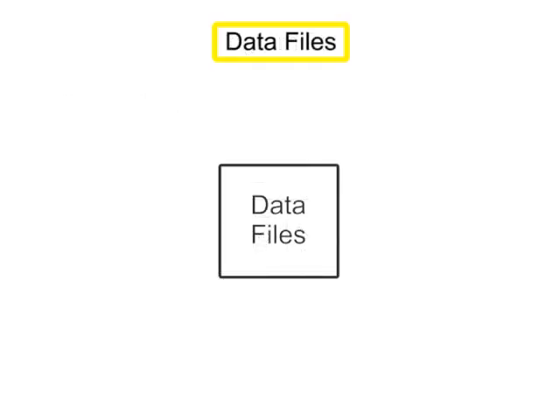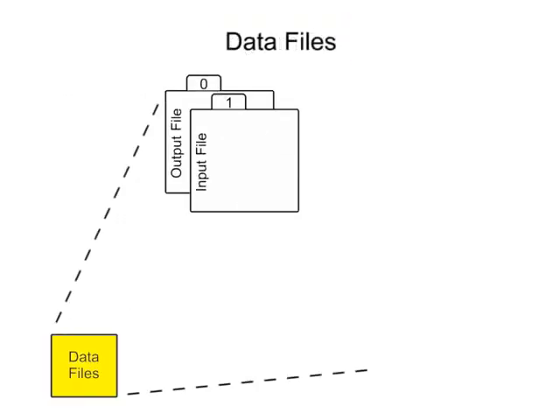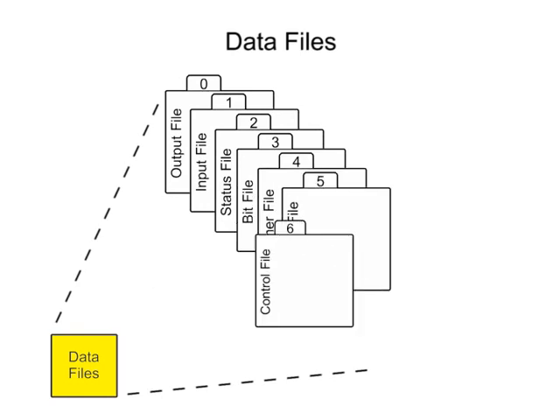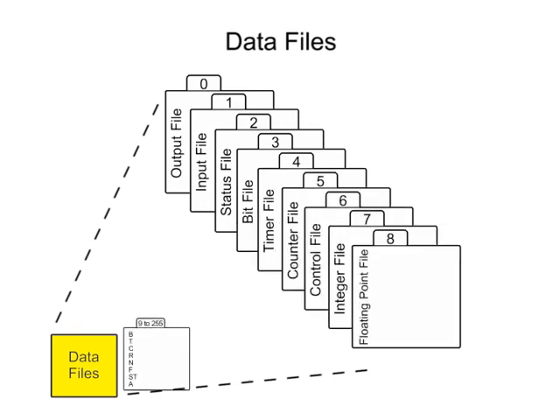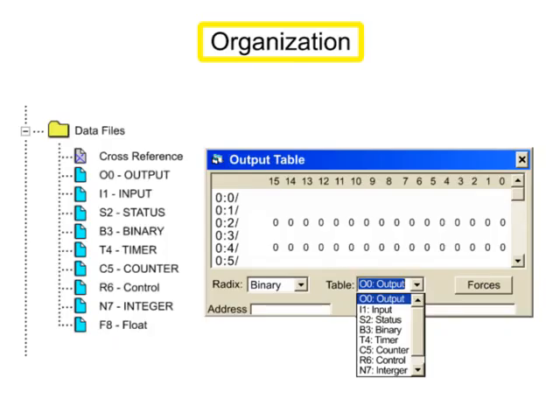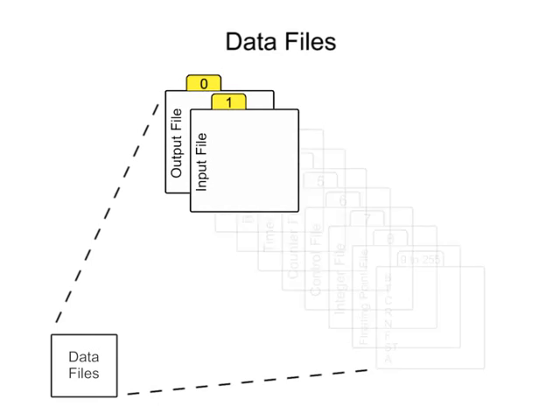Data files store information needed to carry out the user program and is accessed through the ladder logic program. Organization is defined by the type of data they contain and are assigned a file number. Files 0 and 1 are input and output data files assigned to a physical location of a rack and slot, providing an interface to real-world input-output.